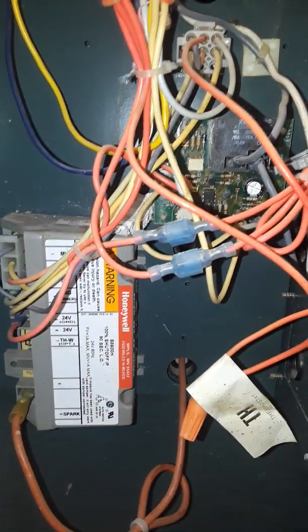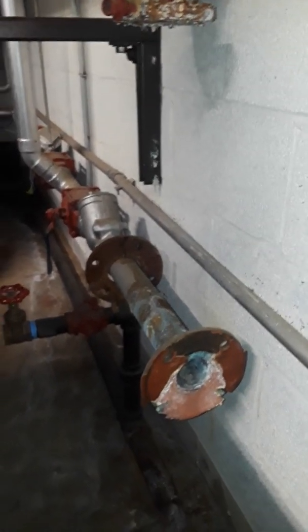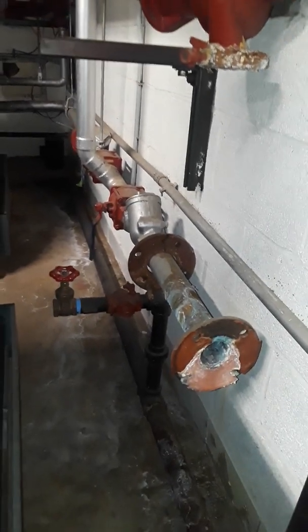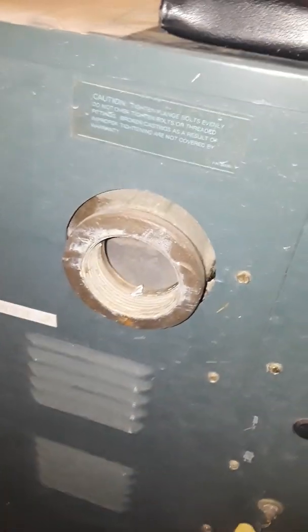Got a little Honeywell ignition control on it. The flow switch has been removed. There's our circulating pump — we need to replace that. There's the in and out, two inch, maybe two and a half.